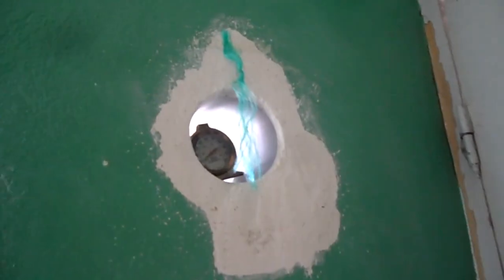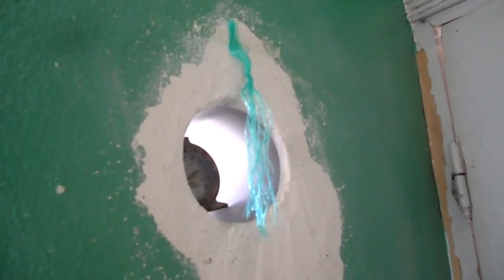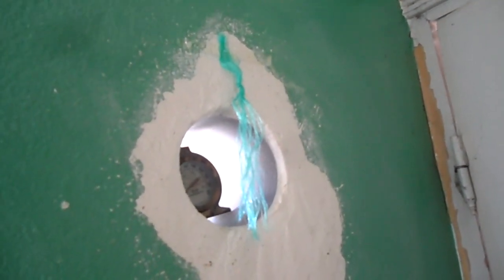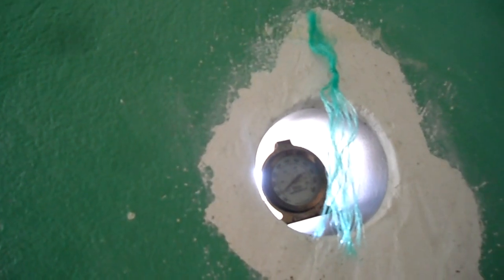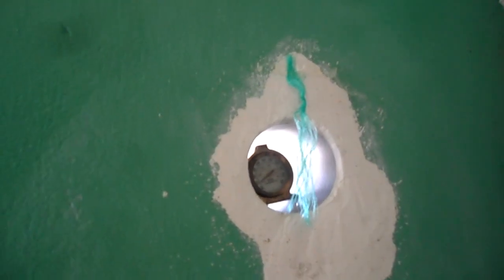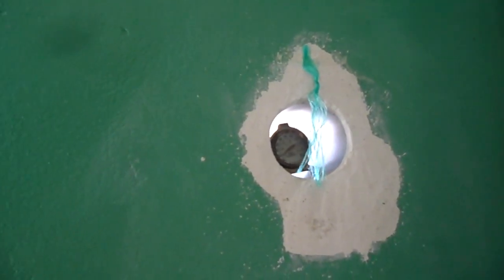To see the entry tubes inside, there's one on the bottom and then one on the top. I hung some string in front of the top tube so that you can see the flow of air coming into the room. Right now it's about 140 degrees entering the room, and the exterior temperature in the shade is probably about 60 degrees today.